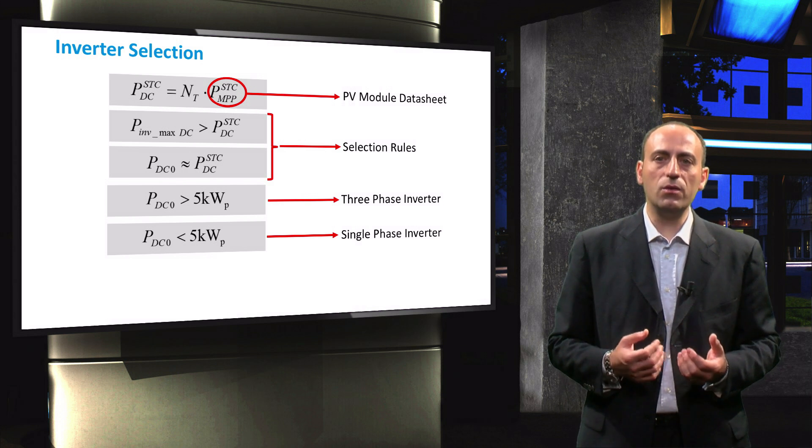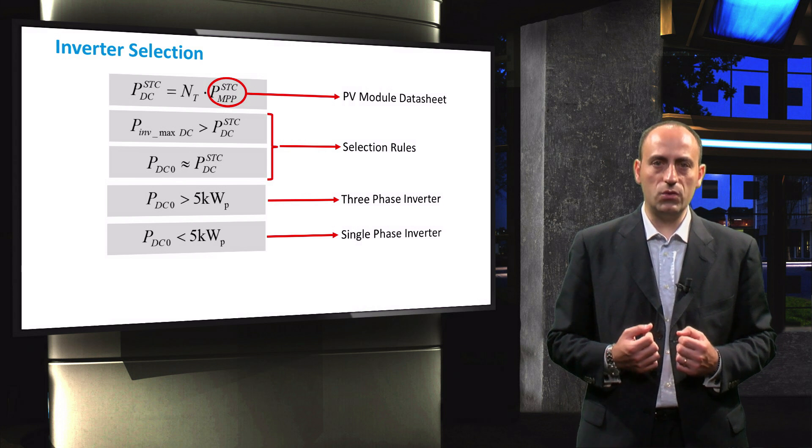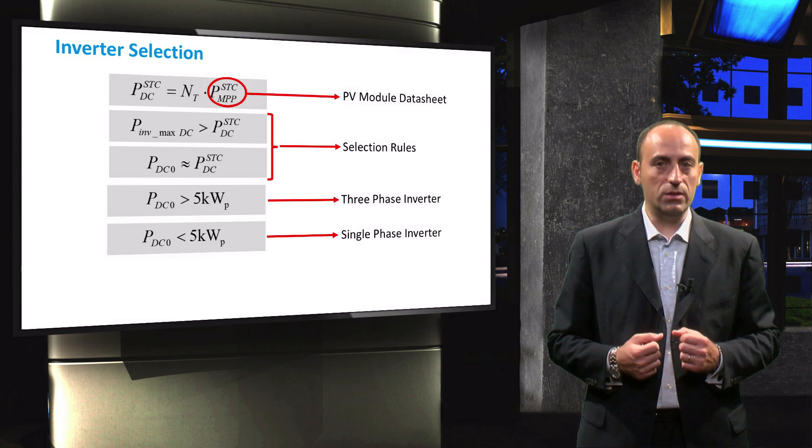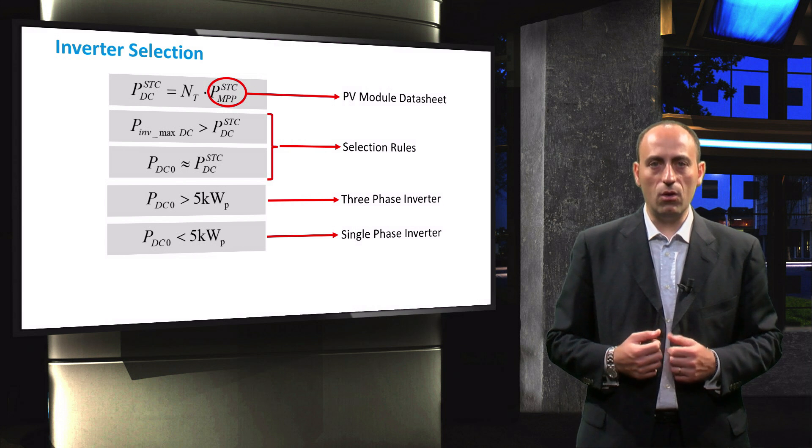Based on these criteria, a suitable inverter can be selected from the market or from the inverter database maintained by Sandia National Laboratory. From the selected inverter, we obtain two important parameters for our grid-connected system design: the nominal AC power, PAC0, and the nominal DC voltage, VDC0, of the inverter.